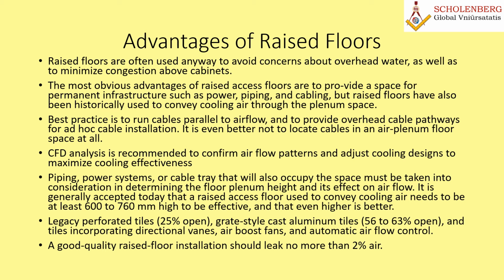The next one is that CFD analysis is recommended to confirm the airflow patterns and adjust the cooling design to maximize cooling effectiveness. If the budget allows, CFD analysis is the best way to predict. The next is that piping, power systems or cable trays that will also occupy the space must be taken into consideration in determining the floor plenum height and the effect on airflow. It is generally accepted today that a raised floor used to convey the cooling needs to be at least 600 to 760 mm high to be effective, and even higher is better because you get space below to properly lay the cables, with minimum obstruction to the airflow.